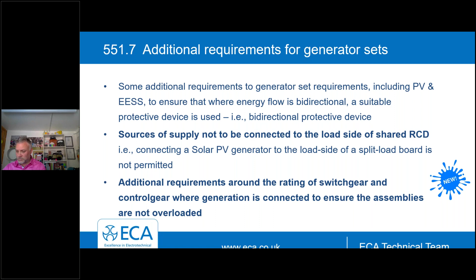Just something to note there: when RCDs are provided for additional protection, in accordance with regulation 415.1, for circuits connecting any generator sets, there must be multi-pole disconnection. That includes the neutral. There's also been an update for the requirements of rated switchgear and control gear when a generator, such as solar PV or battery storage, has been installed. So it's been clarified. This may mean that you have to increase the rating of your switchgear because of the load which is available on the busbar, or you may be able to use certain switchgear with a lesser rated capacity, providing you meet certain conditions and manage the load. There are also updates to the regulation in terms of enclosures which support generators and final loads, and that's in regulation 511.7.2.2. So give that a look as well.